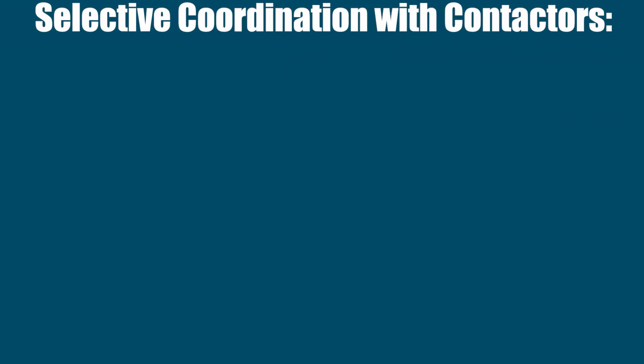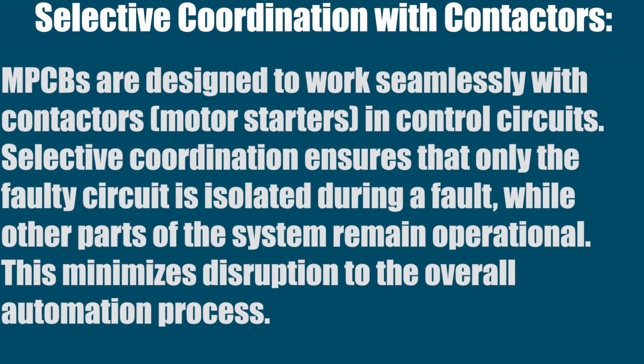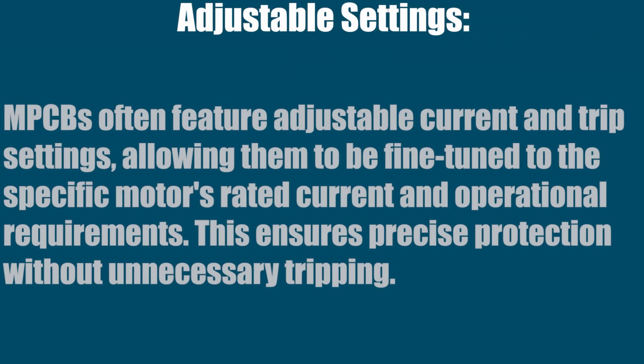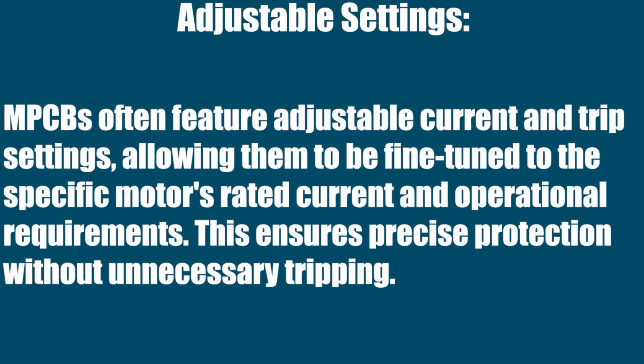So, selective coordination with contactors. Motor protection circuit breakers are designed to work seamlessly with contactors, or motor starters, and control circuits. Selective coordination ensures that only the faulty circuit is isolated during a fault, while other parts of the system remain operational. This eliminates disruption to the overall automation process. Adjustable settings. Motor protection circuit breakers often feature adjustable current and trip settings. This allows them to be fine-tuned to the specific motor's rated current and operational requirements. This makes sure that there's precise protection without unnecessary nuisance tripping.